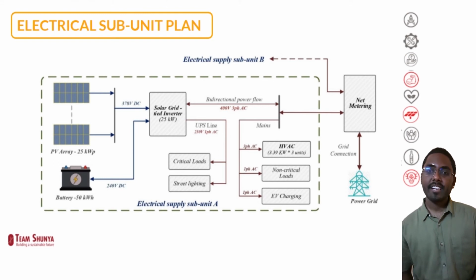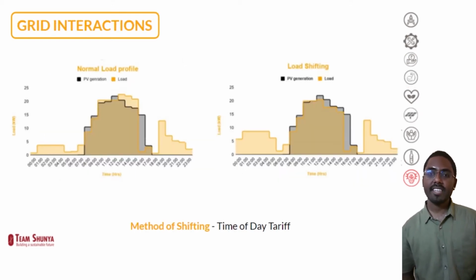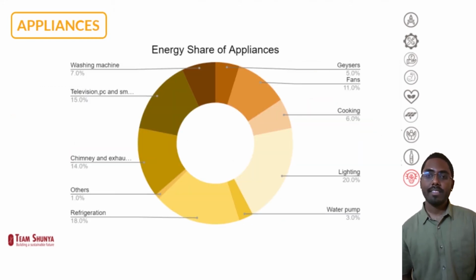Battery is sized such that it should meet the critical loads during grid outage and also the non-HVAC loads during night hours. A scenario was taken into consideration for shifting the load profile during daytime to the midnight hours when the tariff is minimum by using time of day tariff method. This is the share of energy consumption of appliances for each cluster.